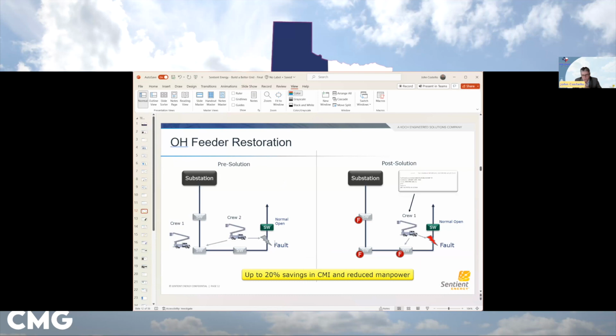In a normal situation, if you didn't have monitoring, all you really know is that that fault is somewhere out there in one of those sections, one of those areas. So you would dispatch 1 or 2 crews, depending on the length of the feeder, to go out there and find out where this fault occurred. If you're doing some monitoring, you can actually determine the location of the fault. It's downstream of this sensor, upstream of this one, and you can direct a crew to a particular location.